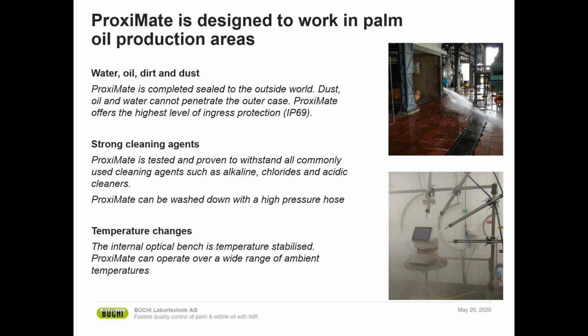In addition, like I said, there's quite often temperature changes in these palm oil production places. They're usually placed close to the palm oil plantations. And again, we've taken that into account during the design of the instrument. The internal optical bench of the ProxiMate is temperature stabilized, and that allows the ProxiMate to be able to operate over a wide range of ambient temperatures. So again, we're able to get good, accurate measurements from the instrument.